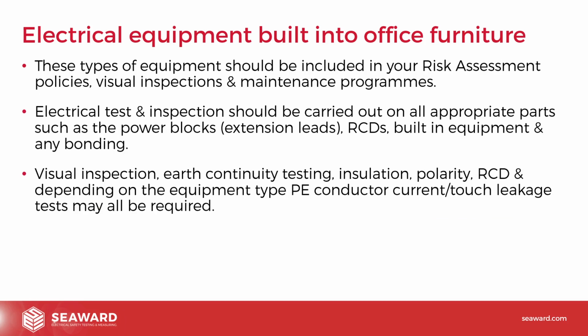These types of equipment should be included in your risk assessment policies, visual inspections, and maintenance programs. Electrical test and inspection should be carried out on all appropriate parts, such as power blocks, extension leads, RCDs, built-in equipment, and any bonding. Visual inspection, earth continuity testing, insulation, polarity, RCD, and depending on the equipment type, PE conductor or touch current leakage may all be required.